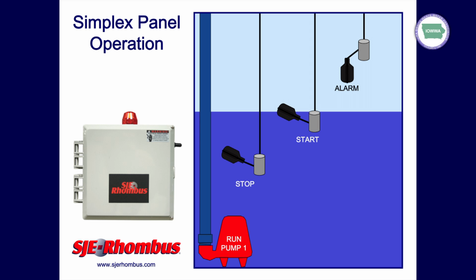Normally open is going to be for pump down. Normally closed would be for pump up. Typically in wastewater situations, where you've got a pump tank that we're going to pump down, it's going to be a normally open switch. If we look at clean water, where you may have a cistern that we're filling up, we want to pump up, then you would use a normally closed switch for that application with the same control panel.